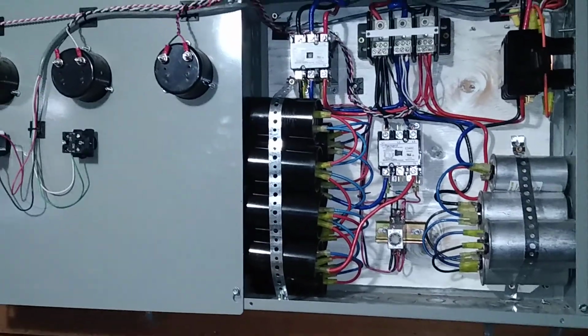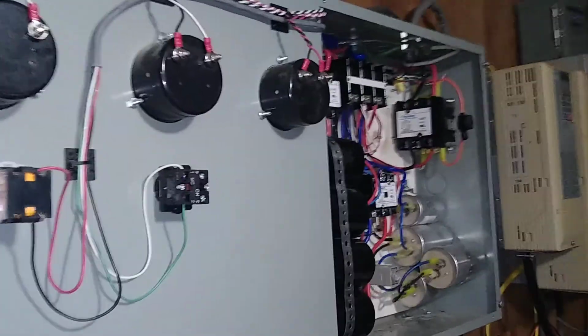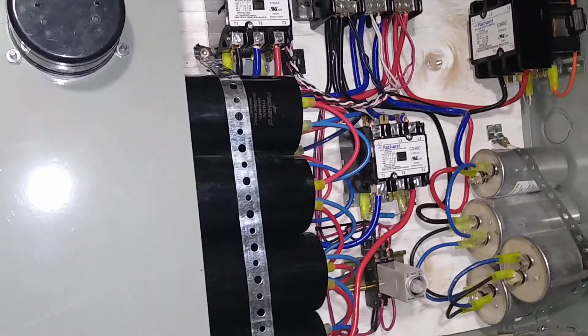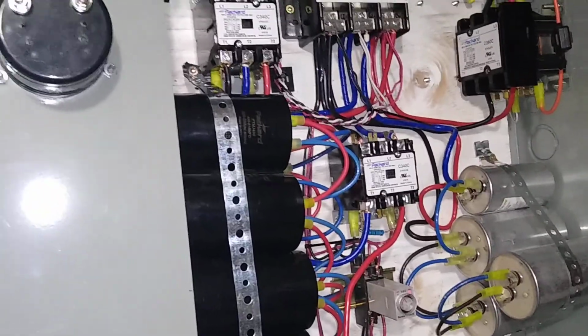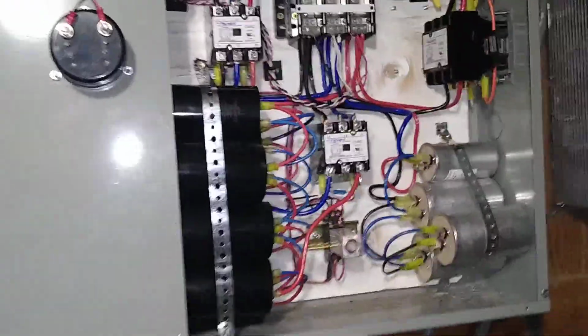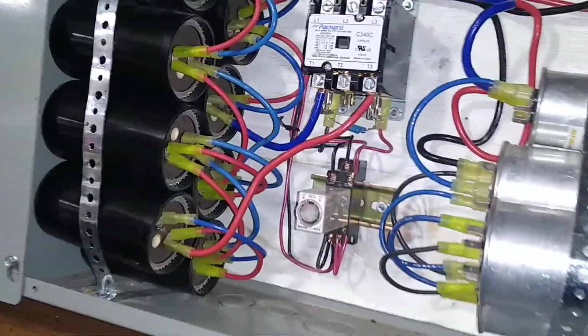But this is her right here. and reach around, start it up. You'll see these two contactors pull in, a little light on the relay. You get a little flash when the start cap contactor pulls out.